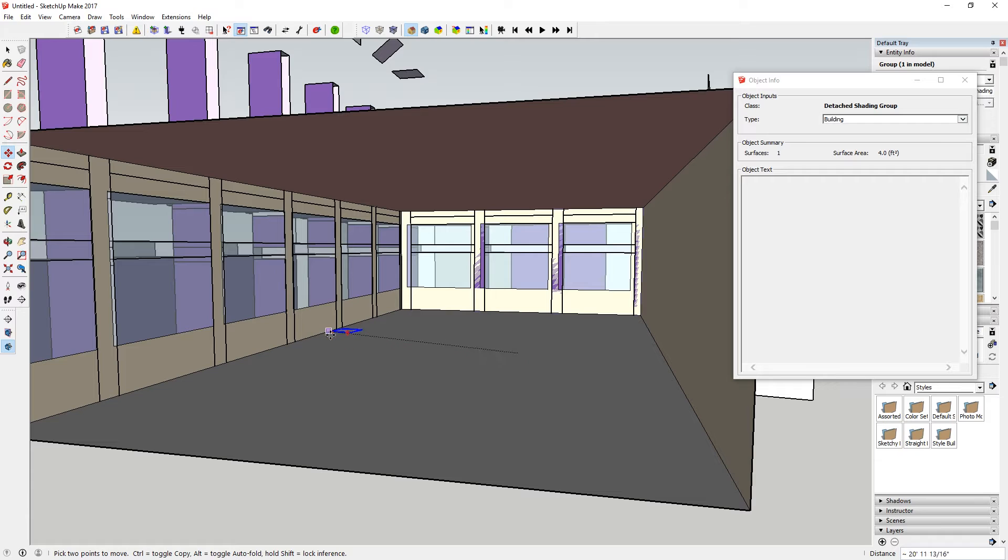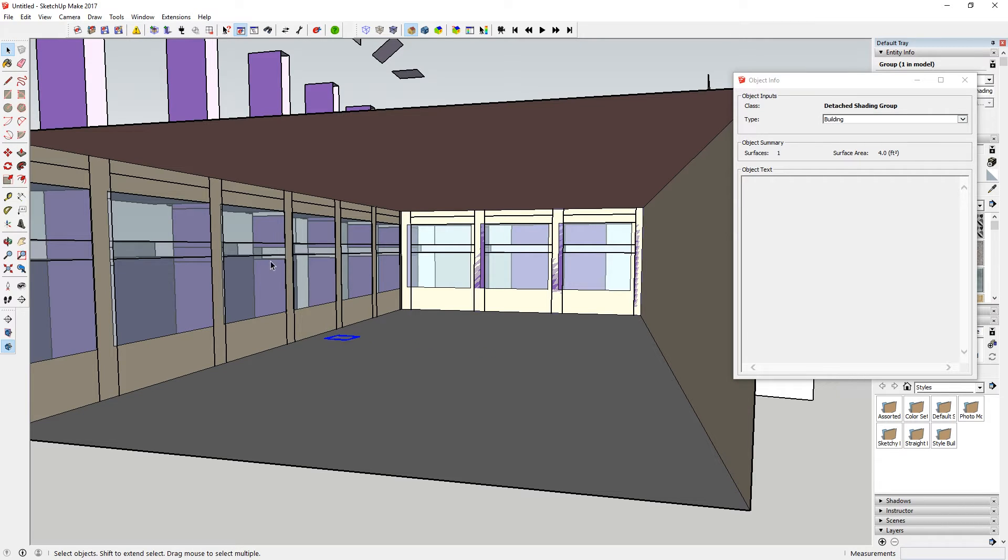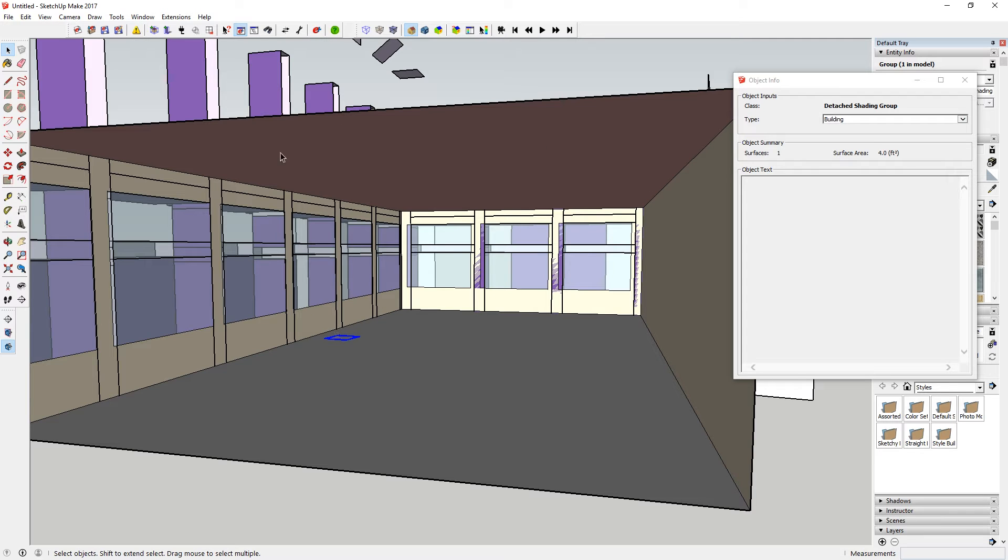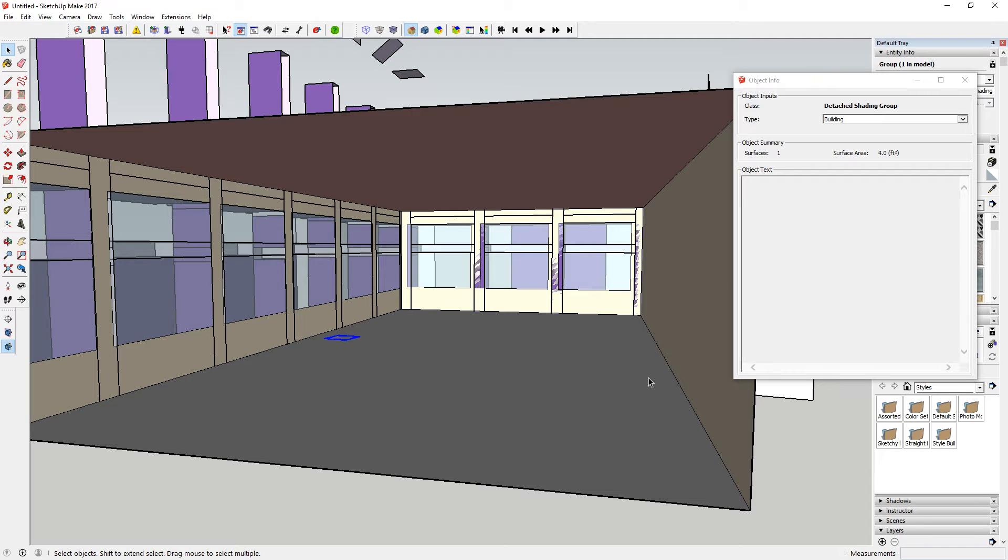So if this sensor is going to drag it over here, then this sensor is going to pick up some high reading and this part of the room in the back is going to be relatively dark. So when this sensor picks up those readings, it's going to dim all of the lights, not just the lights right here, but all the lights for the entire room or the entire zone. And that would mean that the area back here would be really pretty dark.